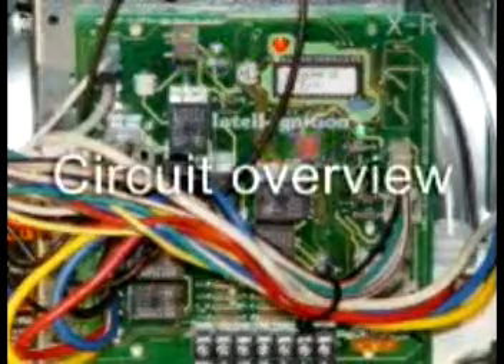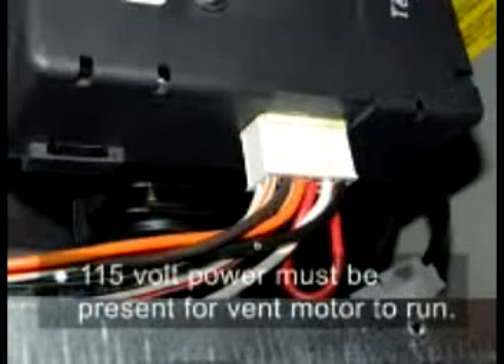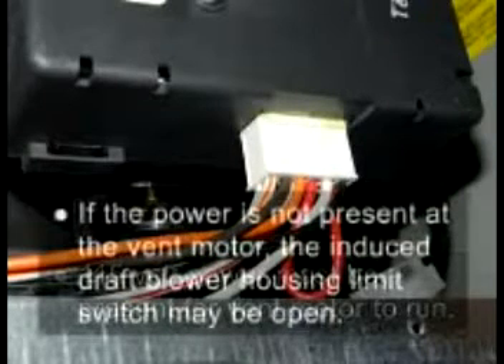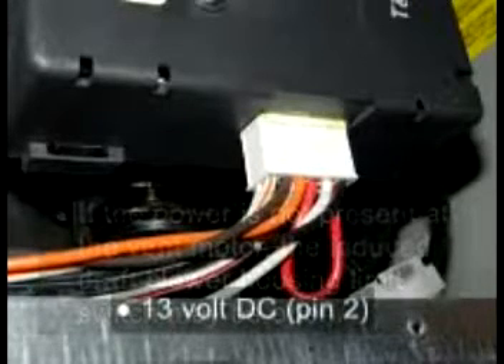Circuit overview. The vent motor has a 12-pin plug that has a line voltage connection. The 115-volt power must be present for the vent motor to run. If the power is not present at the vent motor, the induced draft blower housing limit switch may be open. The 12-pin plug also has a 13-volt DC pin that must have power present for the vent motor microprocessor to function. The 13-volt DC power is received from the IFC board's 5-pin plug.